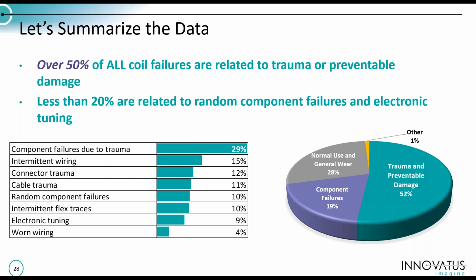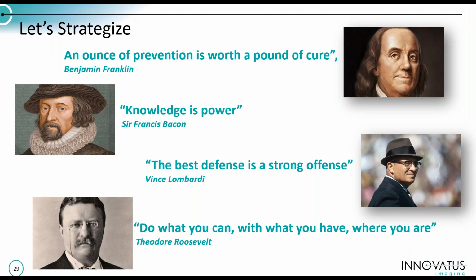So summarizing all of this data, over 50% of all the coil failures are related to trauma and preventable damage, and really only less than 20% are related to random component failures and electronic tuning. With that, let's go back and look at why coil failures or troubleshooting and coil repairs don't necessarily occur in the field. There's only so much you can do with what you have at your fingertips. And so, like I said, you don't have access to the schematics or the specialized test equipment. Knowing all of the information that I shared with you on the last 10 or 12 slides, that knowledge is power, and how you can strategize to reduce your coil failures is going to be revealed in the next half of this presentation.